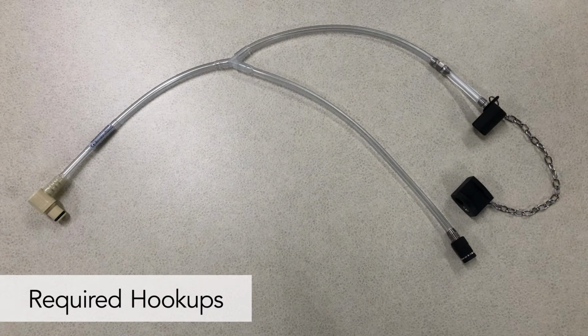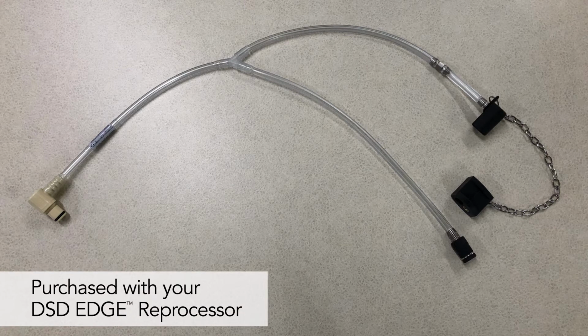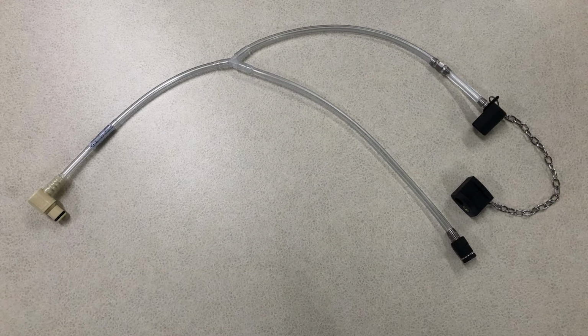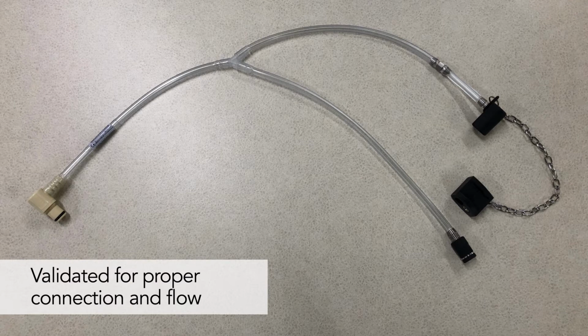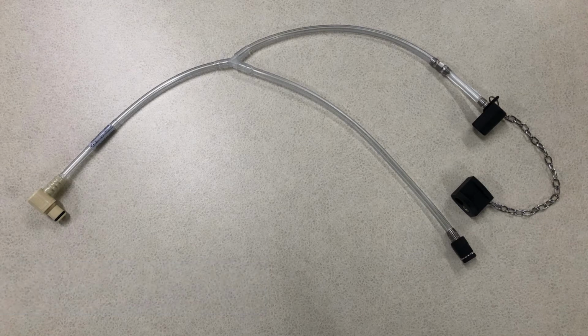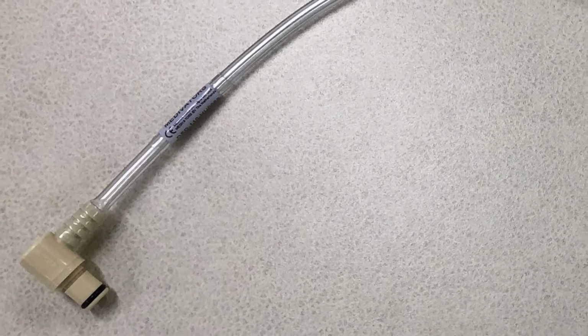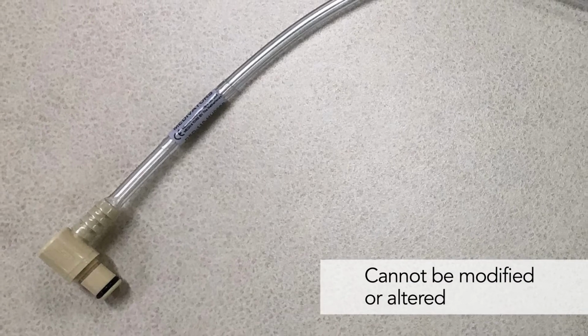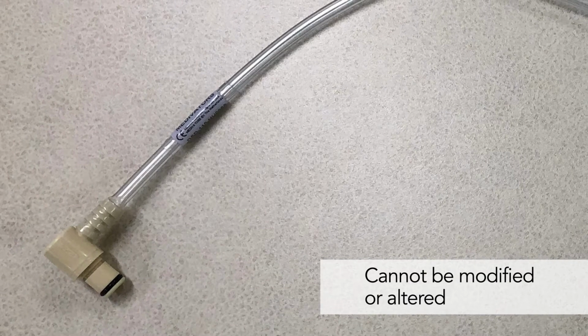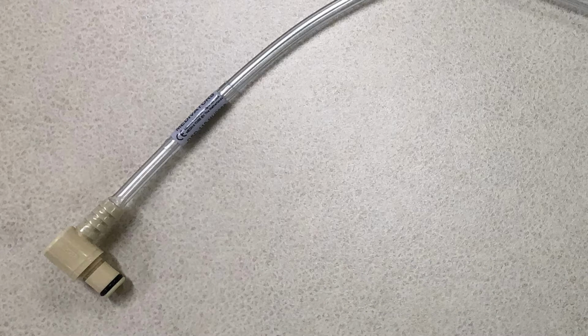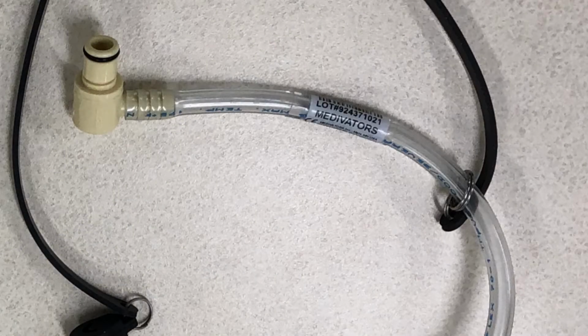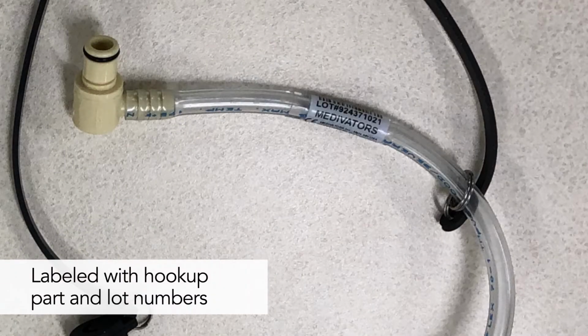Endoscope channel connectors, or hookups, must be purchased along with your DSD EDGE Reprocessor. Only Medivator's validated endoscope hookups can be used. Medivator's hookups are validated for proper endoscope connection and fluid flow, which is critical to ensuring the endoscope and its interior channels are high-level disinfected and rinsed. Hookups cannot be modified or altered. Use of altered hookups is strictly prohibited and will not ensure high-level disinfection of endoscopes or patient safety and should never be used. Each hookup is labeled with a hookup part number and lot number on a label affixed along the tubing for easy identification.